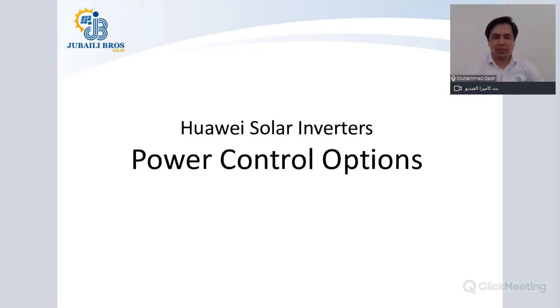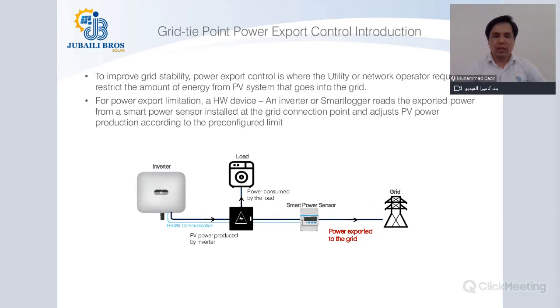So going ahead with the presentation: power control options, grid tie point power export control introduction. In order to improve grid stability, power export control is required, where the utility or network operator requires you to restrict the amount of energy from the PV system that goes into the grid. For power export limitation, multiple Huawei devices might be required. The basic one is the Huawei inverter itself, along with a Huawei power meter or a third-party power meter directly communicating with the inverter, or through a secondary device such as the Huawei smart dongle or smart logger.